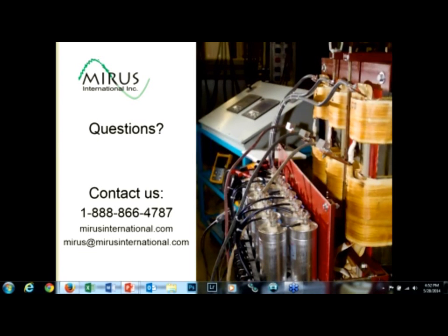It's a question about how the filter might cool itself. Our filters are convection cooled. There's no requirement for any mechanical cooling. And we install the capacitors in the intake air to keep the temperatures of the capacitors as low as possible.